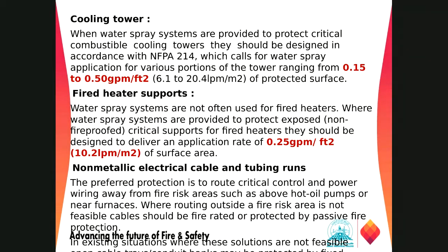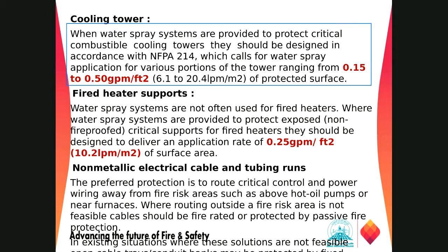And then we need protection for the cooling towers, right? Cooling towers are covered by NFPA 214, which says that water spray systems provided to protect critical combustible cooling towers should be designed in accordance with NFPA 214. Now, NFPA 214 is the standard for cooling tower protection requirements, which requires spray application for various portions of towers ranging from 0.15 to 0.50 GPM.